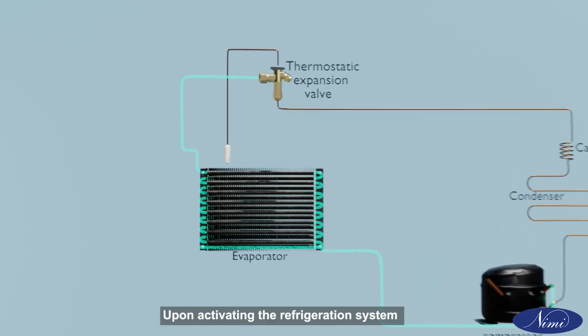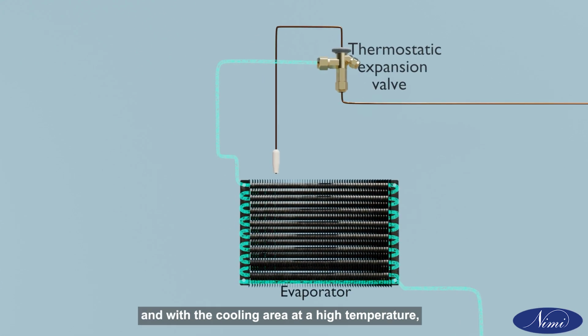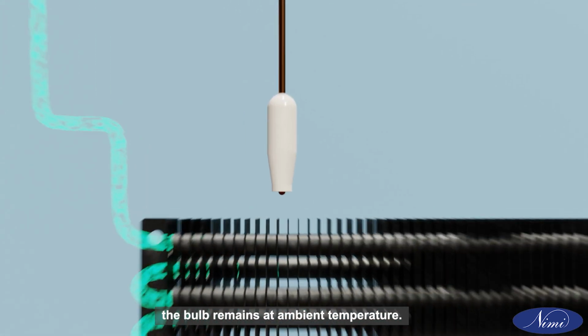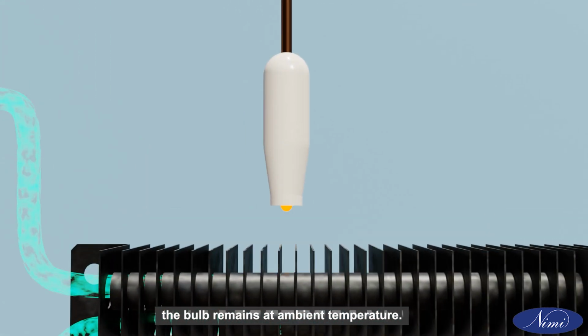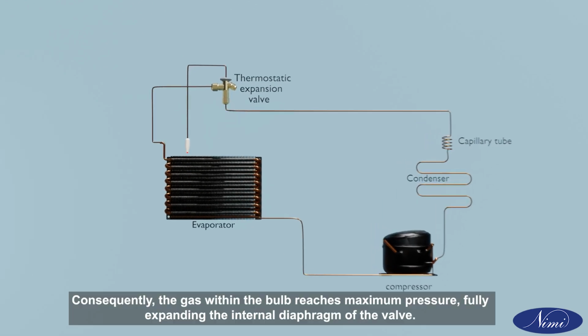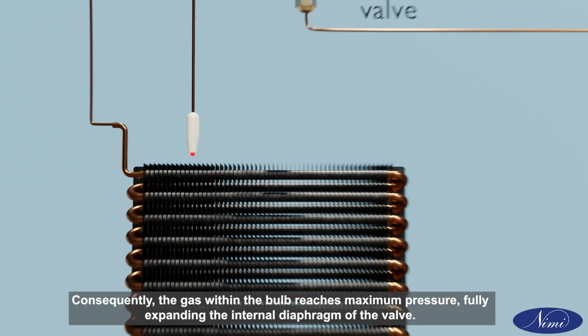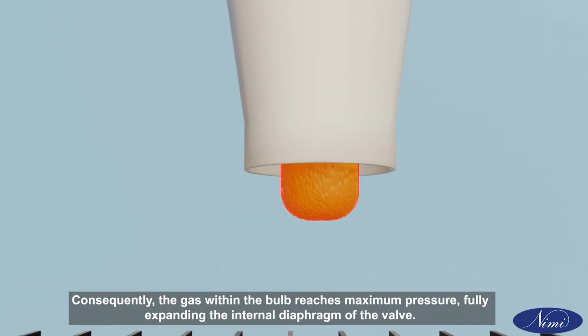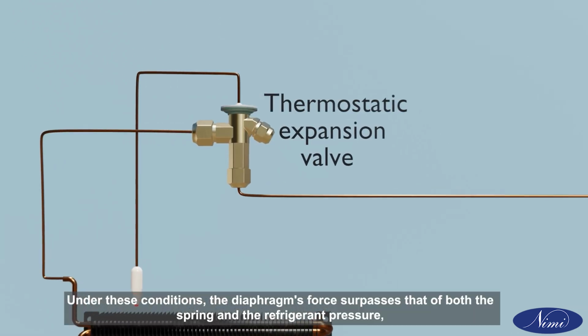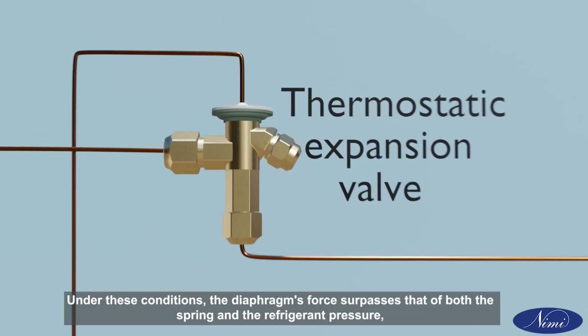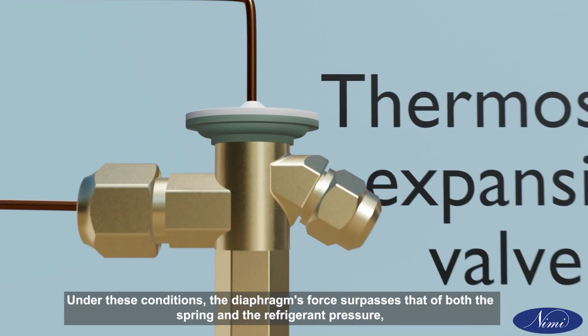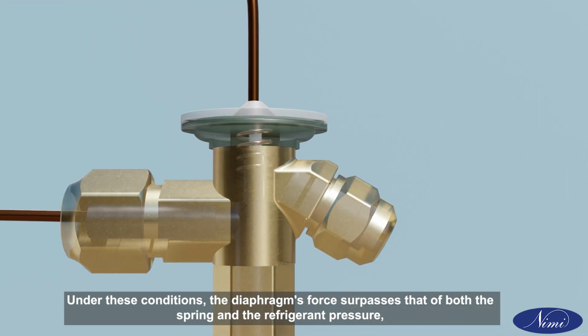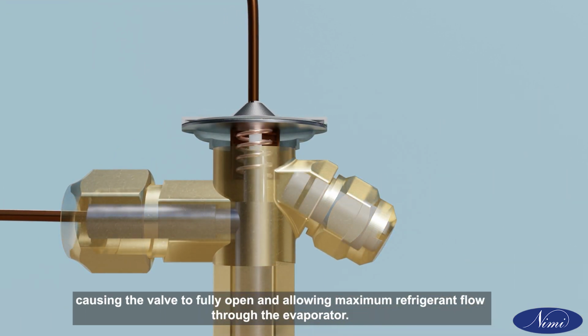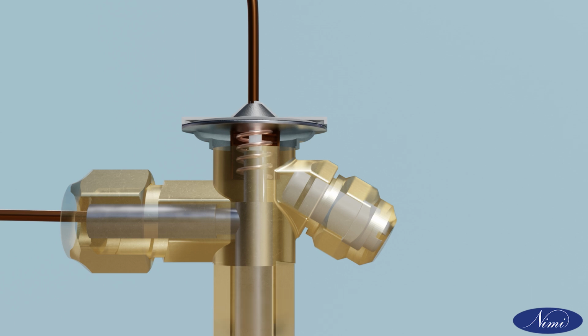Upon activating the refrigeration system and with the cooling area at a high temperature, the bulb remains at ambient temperature. Consequently, the gas within the bulb reaches maximum pressure, fully expanding the internal diaphragm of the valve. Under these conditions, the diaphragm's force surpasses that of both the spring and the refrigerant pressure, causing the valve to fully open and allowing maximum refrigerant flow through the evaporator.